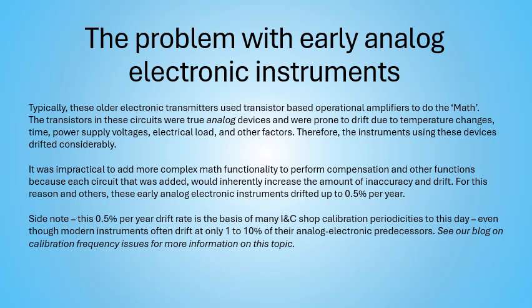Basically, a lot of those instruments drifted up to 0.25% or 0.5% per year. And interestingly, 0.5% per year is what a lot of the calibration frequencies were based on. So a lot of plants still to this day are doing annual calibrations on instruments that drift a fraction of that speed, just because, well, that's the way we've always done it. Sometimes there's other reasons, such as regulatory, or it just makes sense on a SIS, on a SIL3 transmitter. You're going to do things more frequently. But a lot of times, no one's just taken a step back and looked at it. We have another blog on that topic, if you're ever interested.